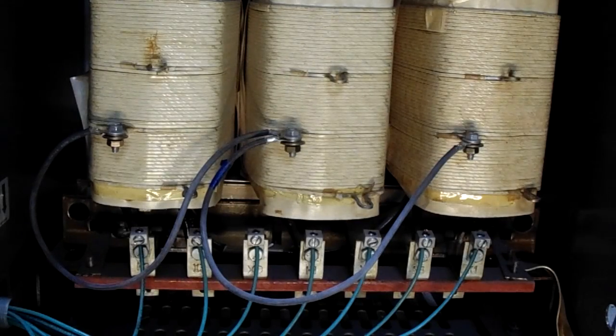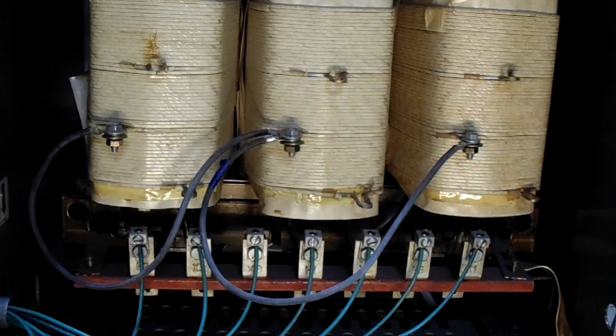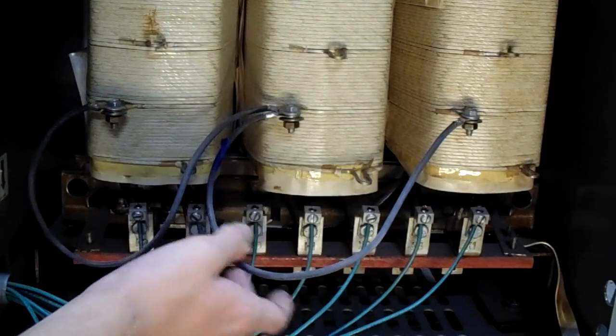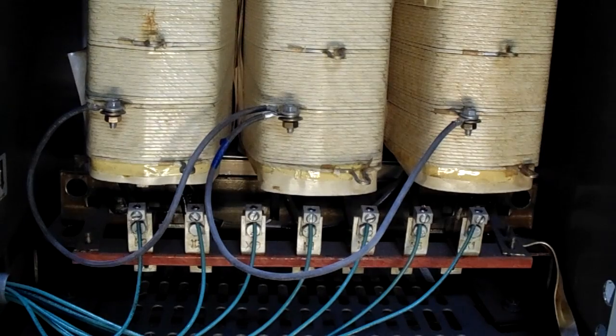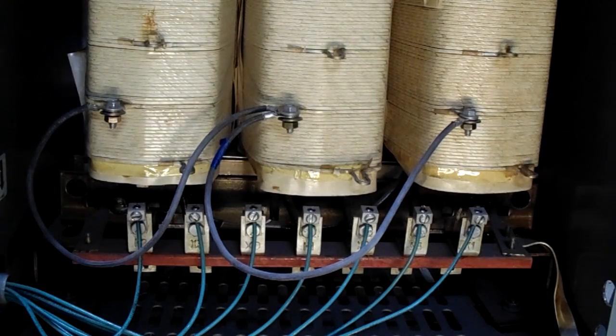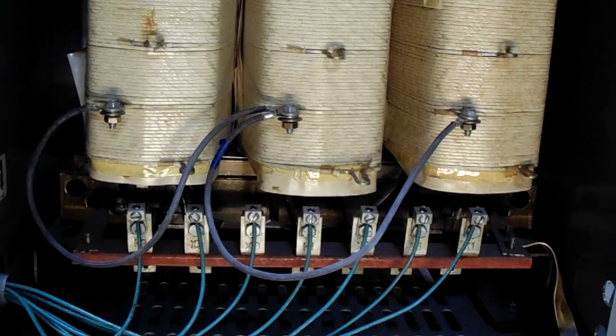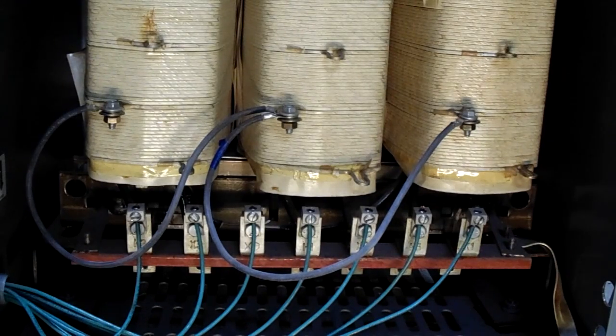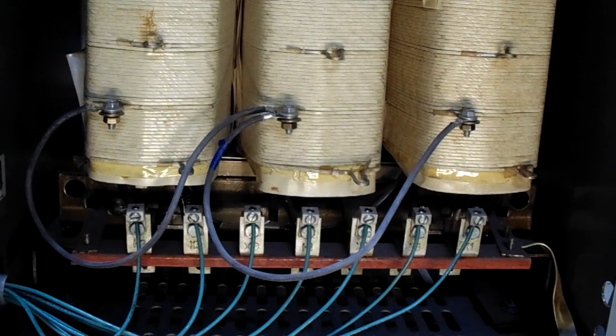Okay, now then, if you're gonna leave your transformer in a star-star configuration, this is probably the way to go, with just wires connecting the taps. If not, then I'd recommend going with a contactor to switch it between star or delta, or however you want to configure that high side or low side, depending on what kind of transformer you have.